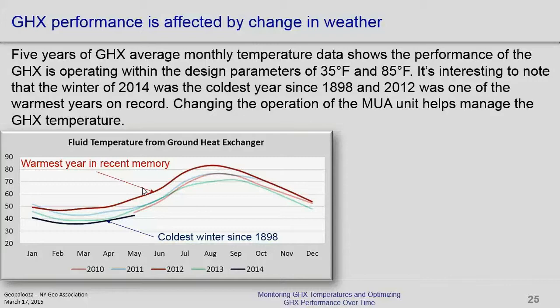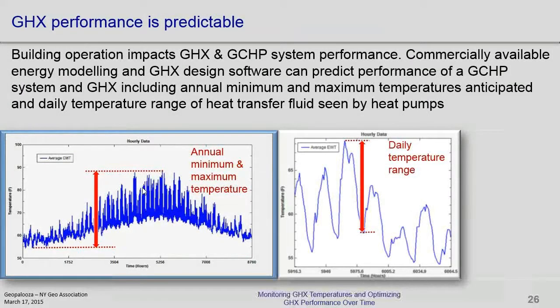So if they know this is about what the temperature range should be, and let's say they're up here all of a sudden, or down here all of a sudden, then they know there's an issue somewhere in the system. They should also know what the daily temperature range is going to be on a typical day. With an hour-by-hour energy model plugged into a ground heat exchanger model that can do hourly loads, you can predict what that temperature should be on a typical day. In this case, the building operator understands the system well enough. It's not that complicated a building, and he's doing it.